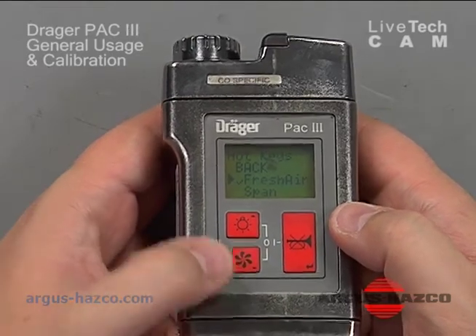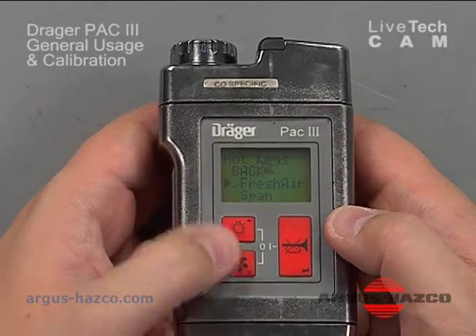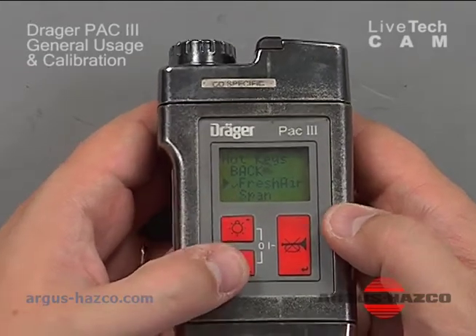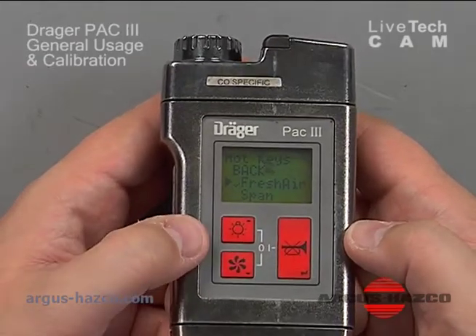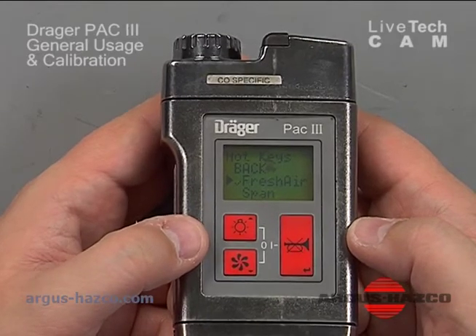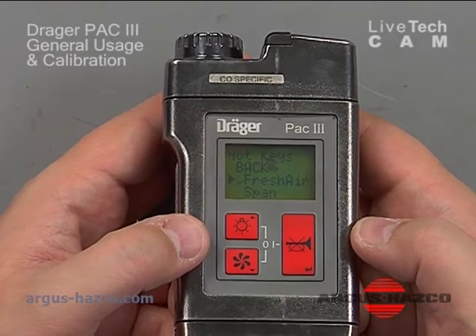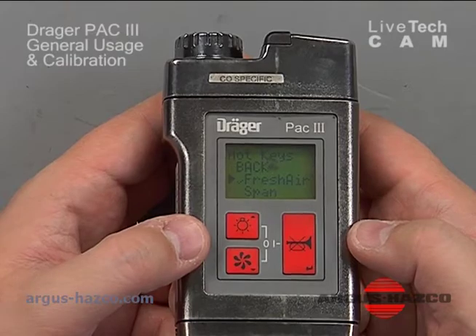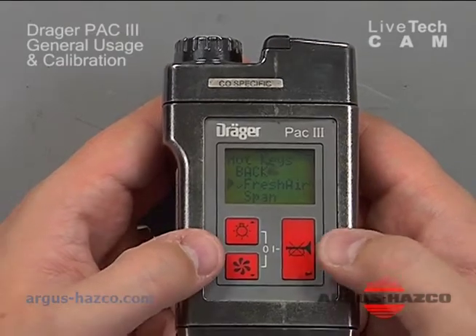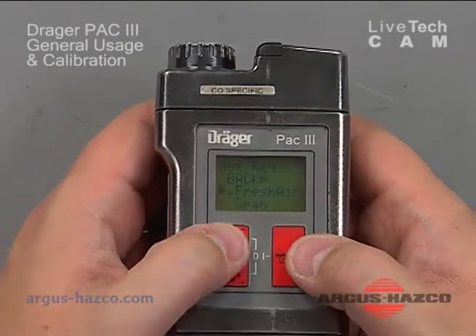The fresh air would be this one as a hotkey. The span would be the top one for a hotkey. You typically don't want to set the span as a hotkey because you don't want people going into a span mode without having the calibration gas present, entering through that, and then throwing off your calibration. So typically you just leave your fresh air adjusted. You click the back button.